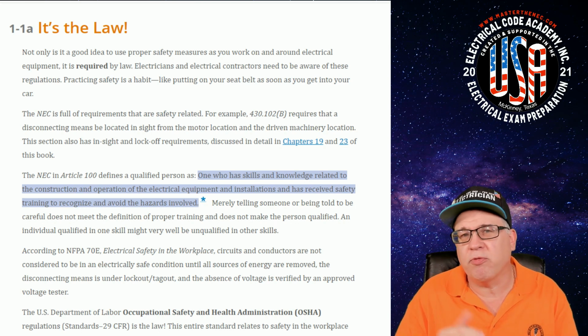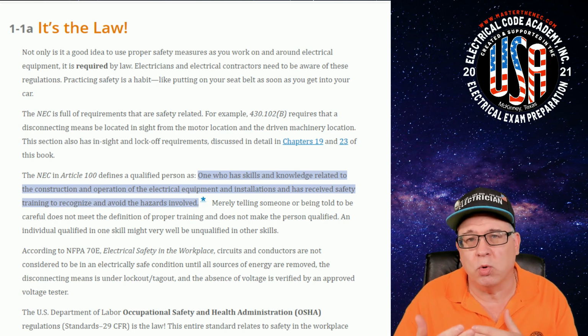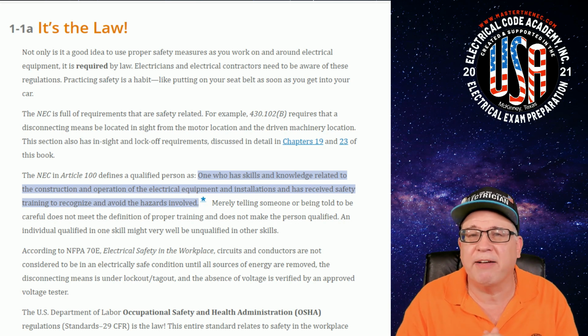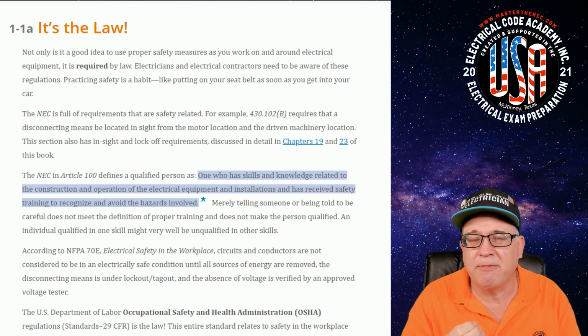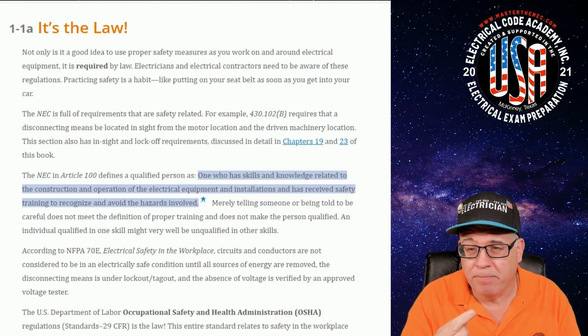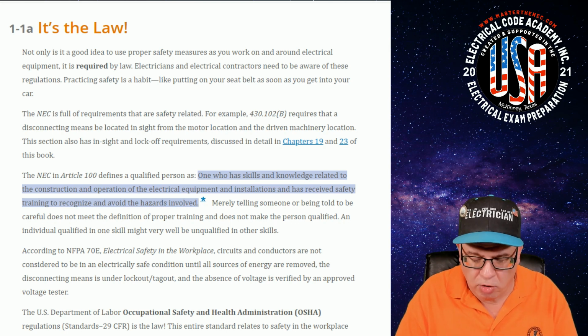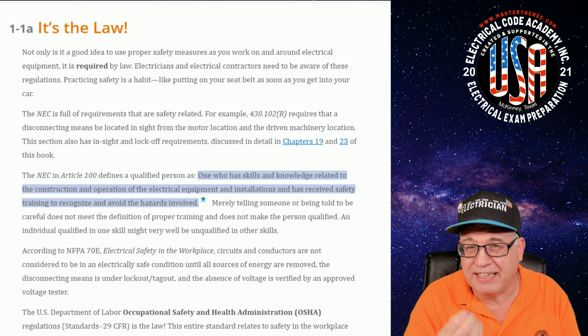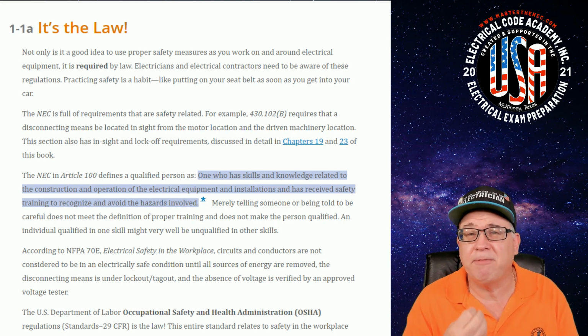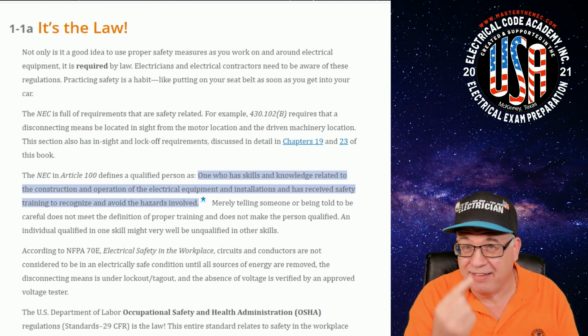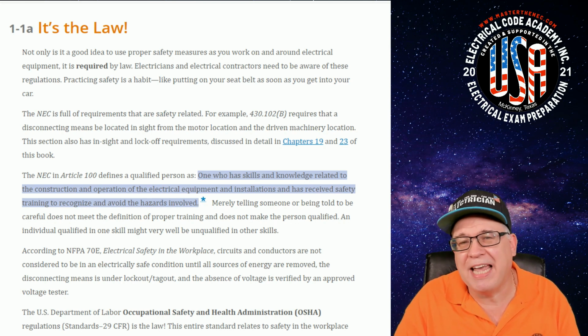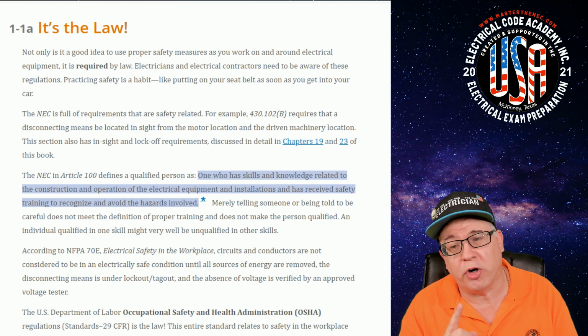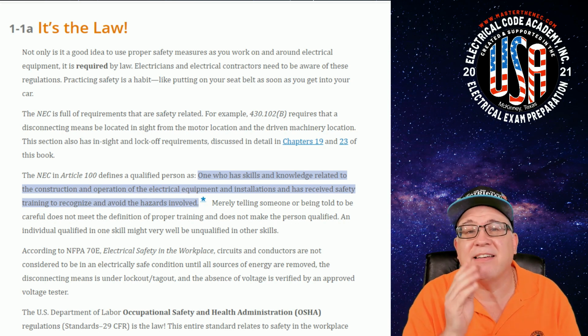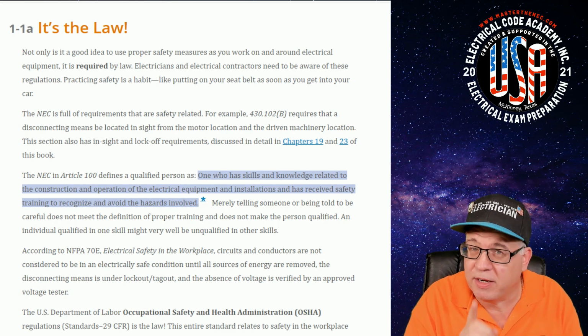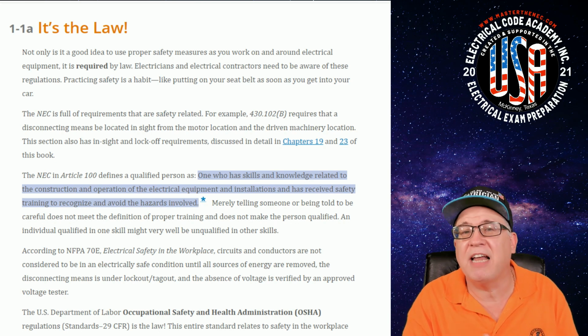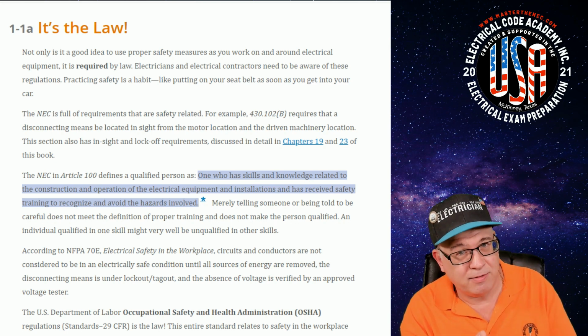There are occasions, for example with the within sight rule, as you see in Article 100 definitions, it has to be within 50 feet and visible to be within sight. So anywhere in the code that says a disconnect has to be within sight, it's got to be within 50 feet of the equipment and within sight. If it was 48 feet from the equipment but around the corner and not visible, it doesn't meet the within sight rule. Just because it's within 50 feet doesn't mean it's within sight.